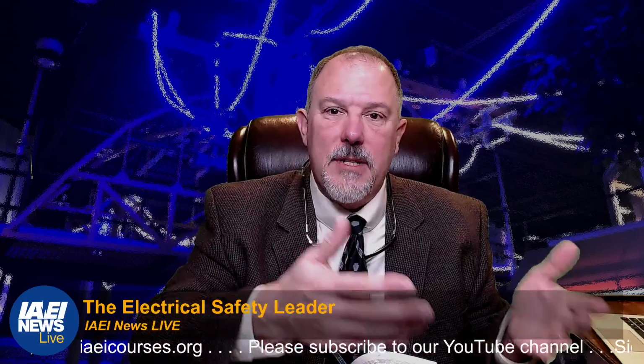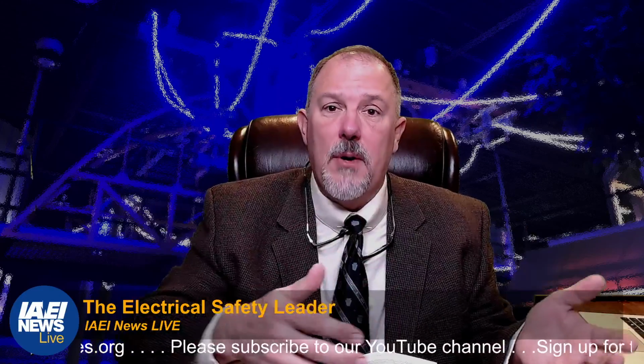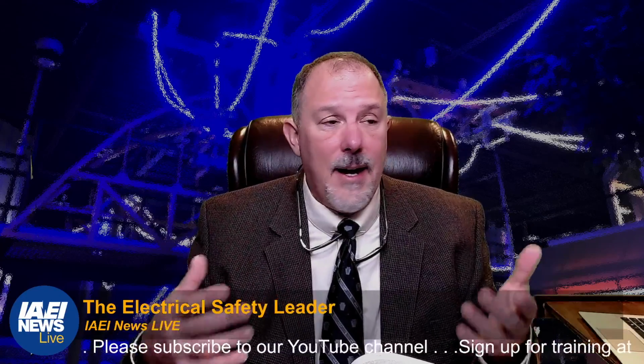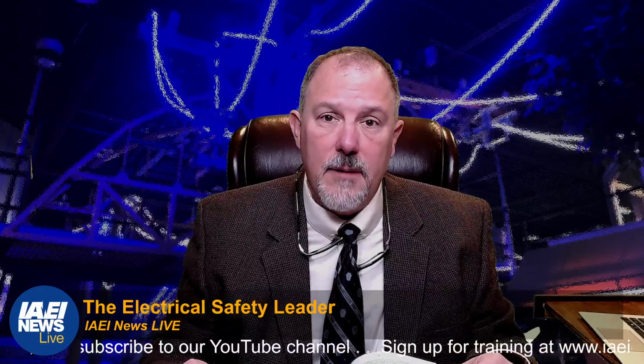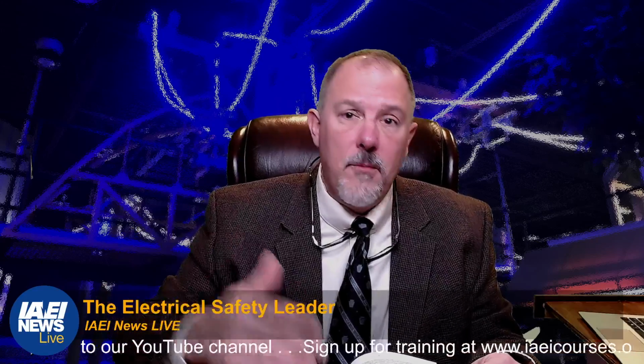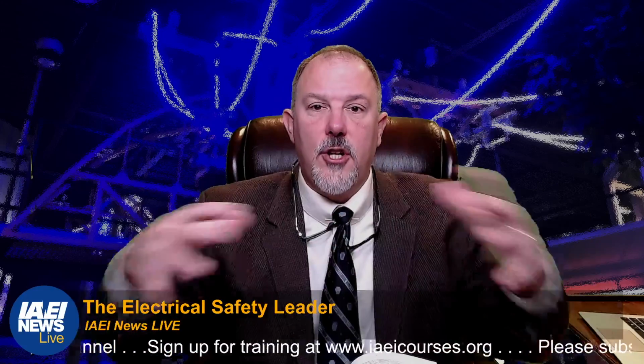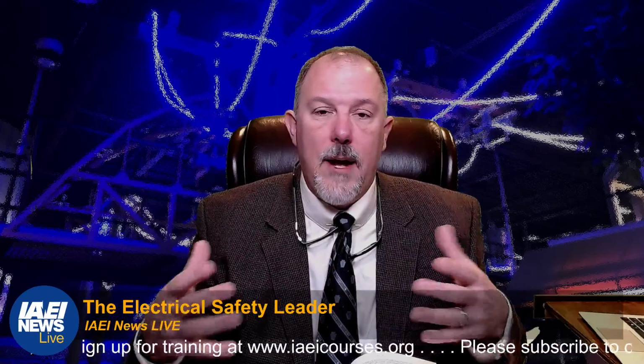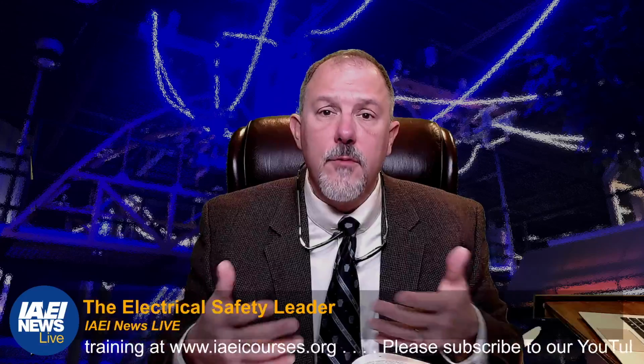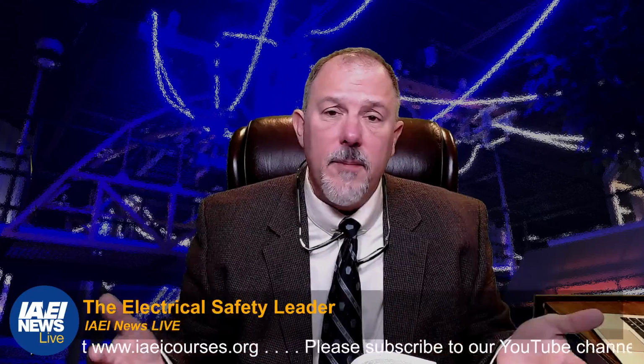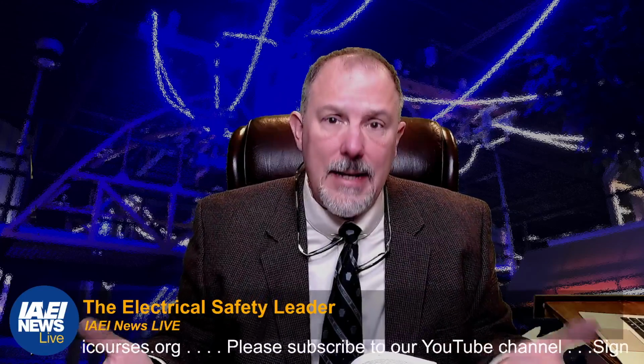That lightning protection, that very large impulse due to a direct hit, I don't know much that can protect you from that. And what do we do there? We move into grounding, and we move into creating those shields so the current has paths to flow around, say, a structure, and hopefully not through a structure. But there's not much you can do for a direct lightning hit.